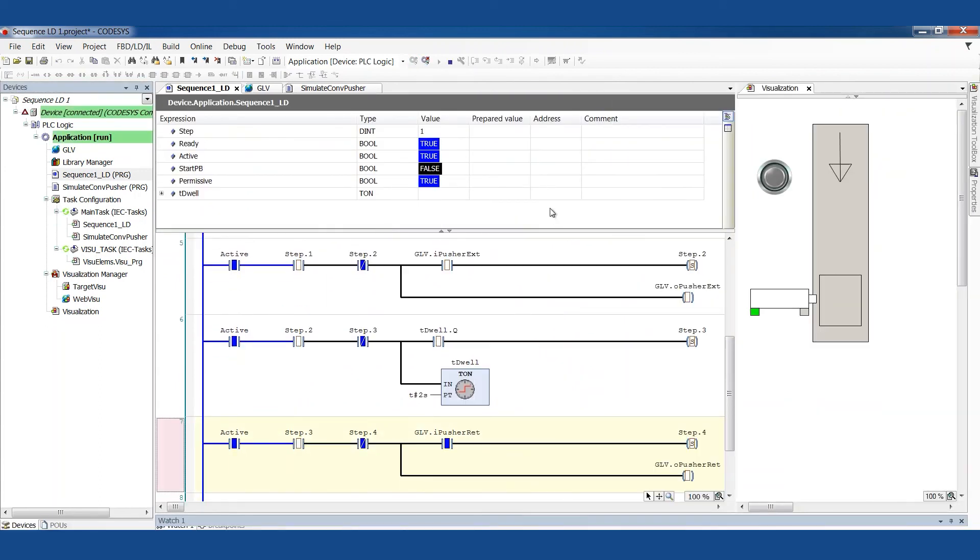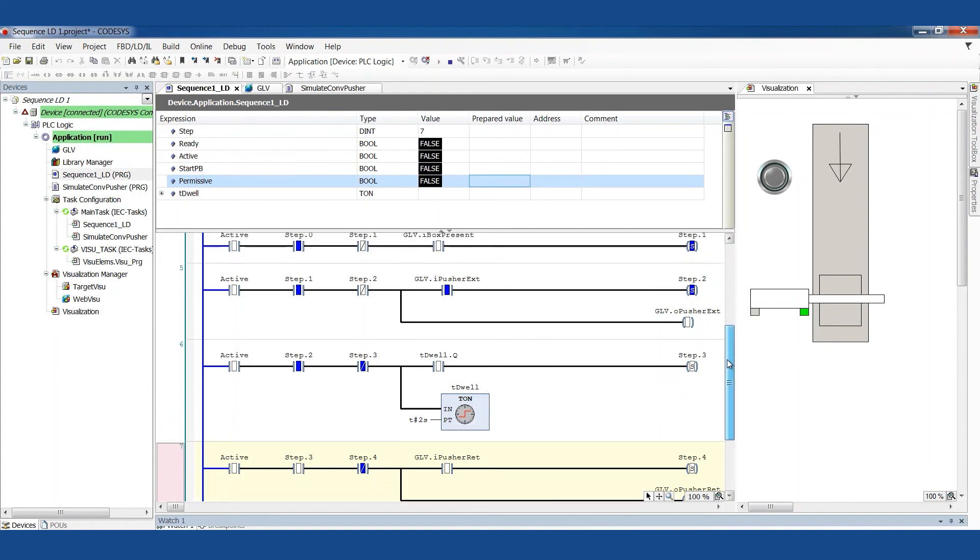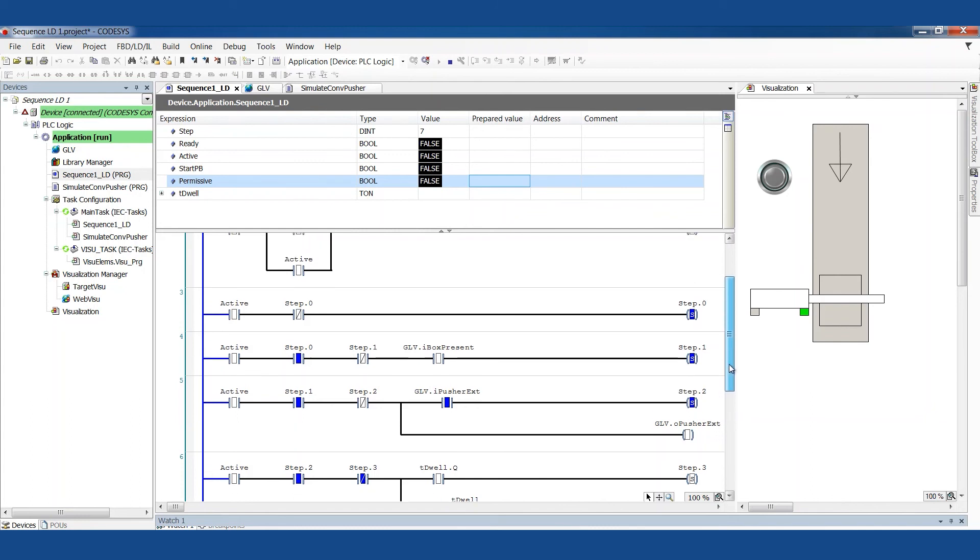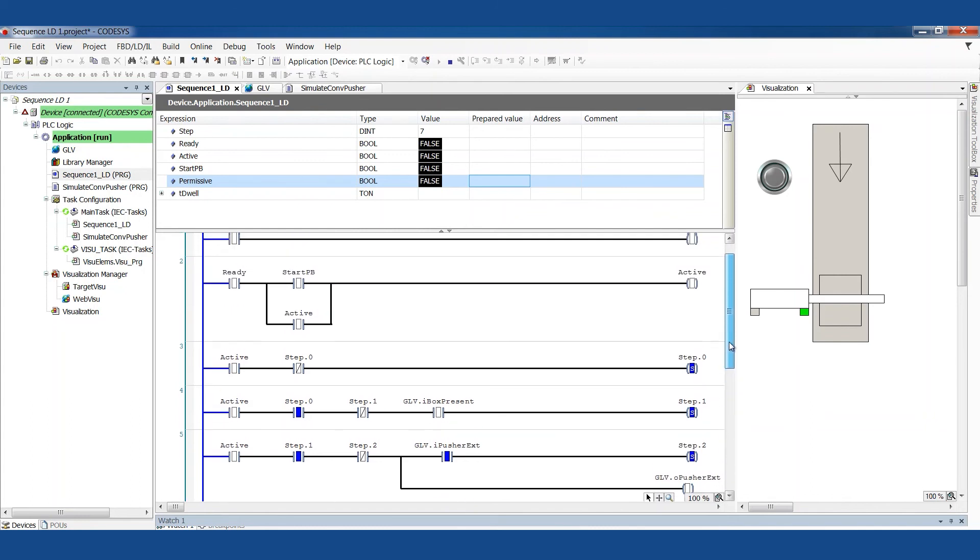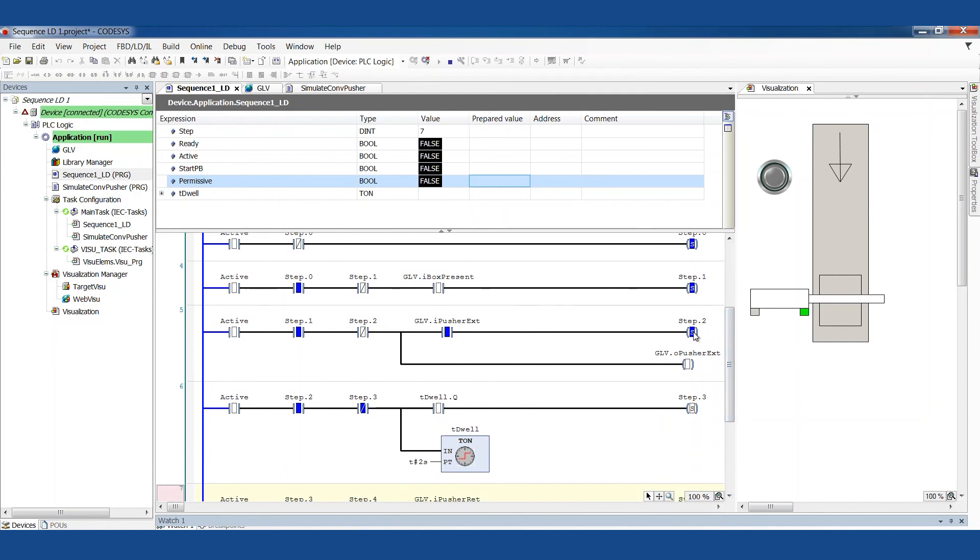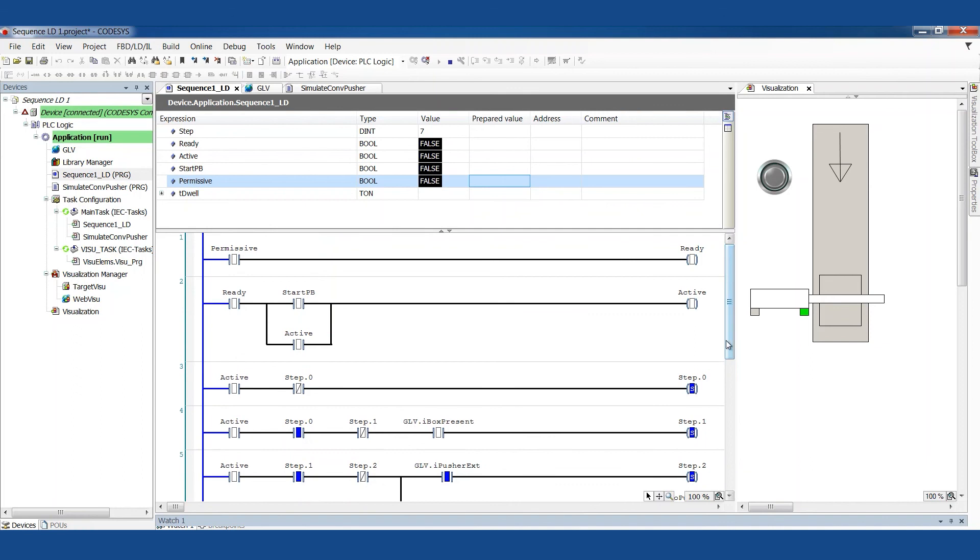For example, simulate again. Let's give this a box and then halfway through running, I'm going to kill the permissive. Notice it still remembers where it is. So if I start it up again, it's just going to pick up where it left off. And in this case, I do want this to retract. That's a good thing. If I clear the sequence entirely, now I'm going to have to have some sort of all retract function or reset the machine function or something like that. But I want you to be aware of this because you don't always want the process to pick up exactly where it was.